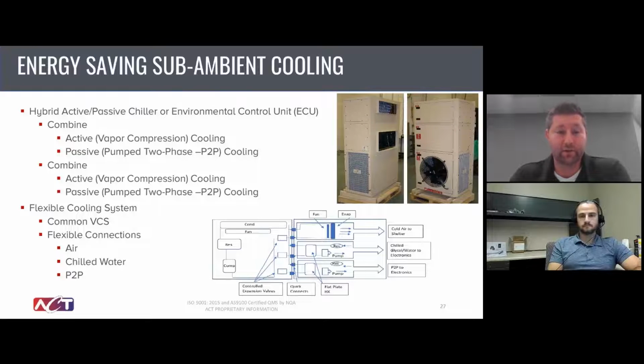But there is an ideal area where you can combine vapor compression systems with pump two-phase cooling and take advantage of pump two-phase anytime that you don't need that critical subambient cooling, and only turn on your compressor when your above-ambient cooling is not available, when it's hot or sunny out. In most applications, pump two-phase can be used the lion's share of the time, and you're designing a vapor compression system for that one use case that happens maybe a couple times a year or one time a day. You're really using a lot of energy to run that compressor all the time, whereas a coupled system using both the active and passive side of things can help reduce energy long term.